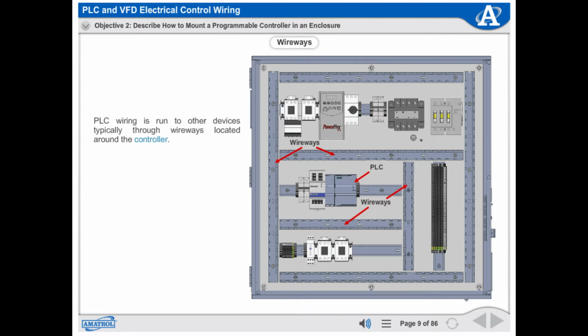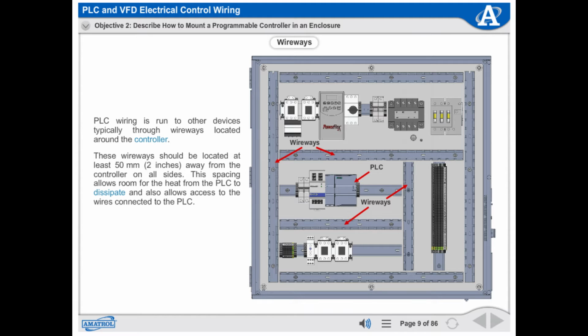PLC wiring is run to other devices, typically through wireways located around the controller. These wireways should be located at least 50 millimeters or 2 inches away from the controller on all sides. This spacing allows room for the heat from the PLC to dissipate and also allows access to the wires connected to the PLC.